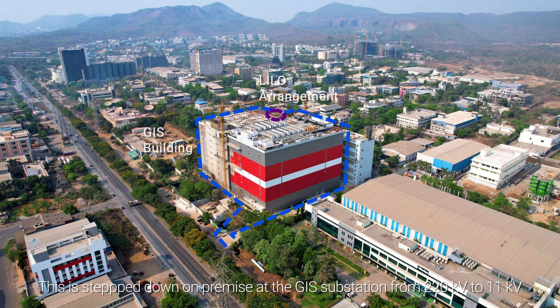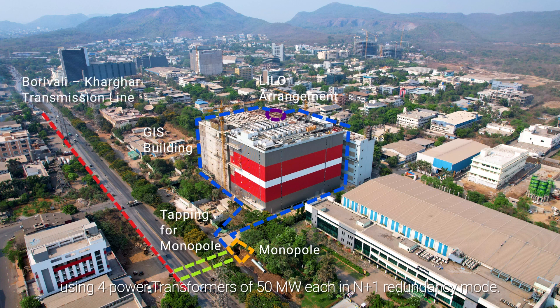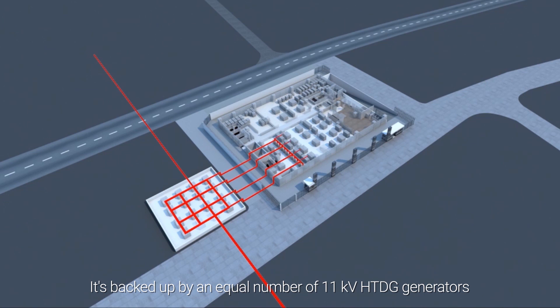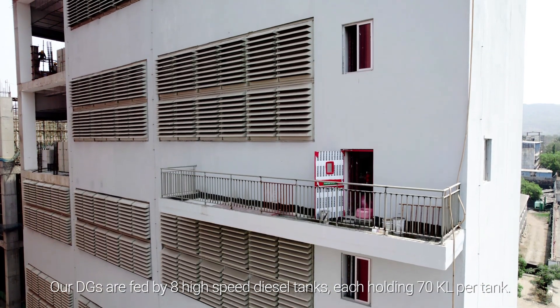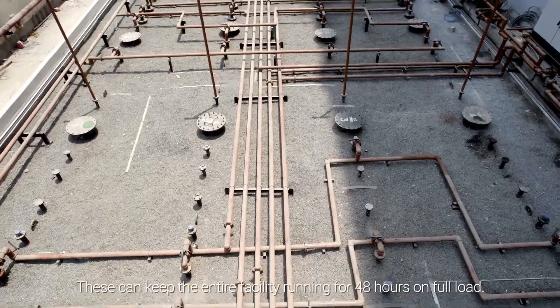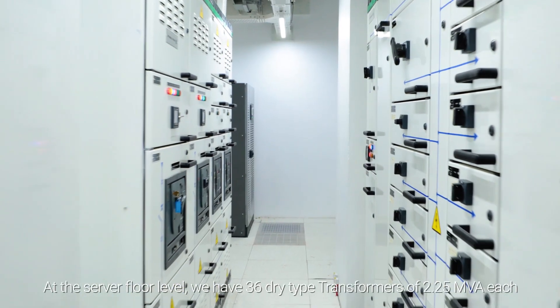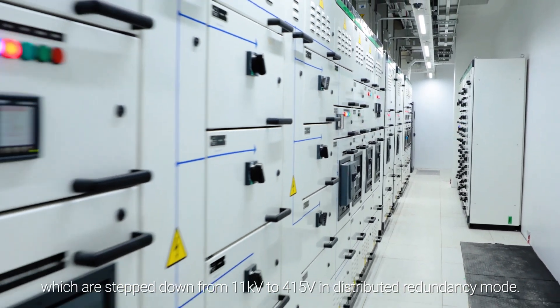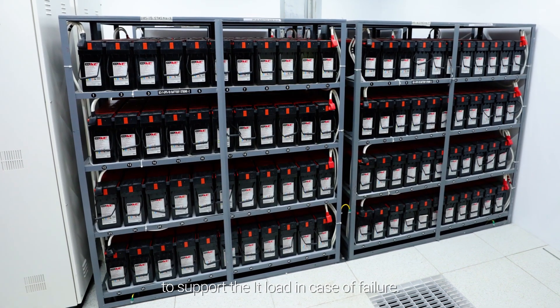Let's move on to the electrical room. The campus receives power at 220 kV with a line-in line-out arrangement. This is stepped down on-premise at the GIS substation from 220 kV to 11 kV using four power transformers of 50 megawatt each in N+1 redundancy mode. It's backed up by an equal number of 11 kV HT DG generators of 2.25 MVA each in N+2 redundancy mode. Our DGs are fed by 8 high-speed diesel tanks each holding 70 kL per tank, which can keep the entire facility running for 48 hours on full load. At the server floor level, we have 36 dry-type transformers of 2.25 MVA, stepping down from 11 kV to 415 V in distributed redundancy mode. We also have an additional UPS battery backup of 10 minutes to support the IT load in case of a failure.